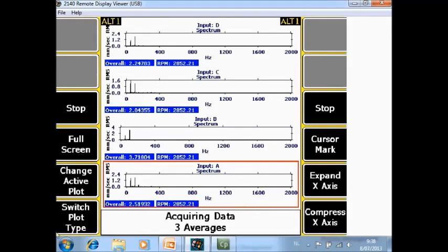And during data collection, I will make a zoom in this range to see it better. And you see the 50 Hz or 49 is staying stable, but the 100 Hz is disappearing from the spectrum. So before it was more than 2 mm, now it's close to 0. So if you see that the data is stable, you can stop the process by clicking F9 Stop.